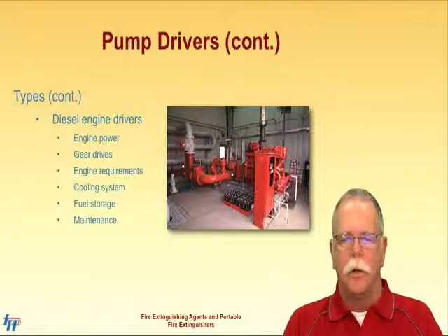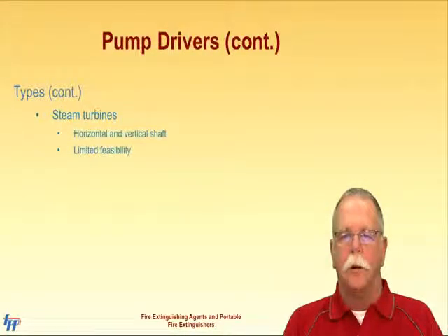Diesel engines are required to have engine system monitoring and battery maintenance equipment to ensure proper operation. Fuel storage and the amount of maintenance that is needed for a diesel engine, in contrast to the low maintenance needs of an electric motor, are detractors of the effective diesel engine. You will likely not see a steam turbine pump driver over the life of your career. The need for an uninterruptible source of steam makes them impractical.